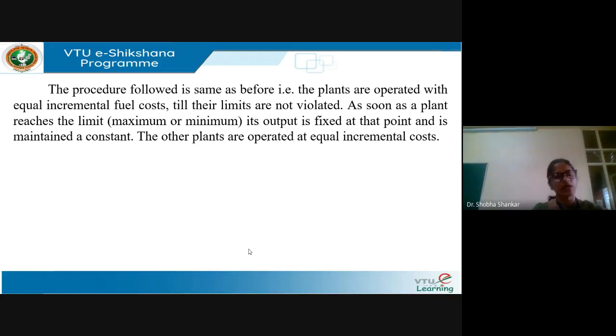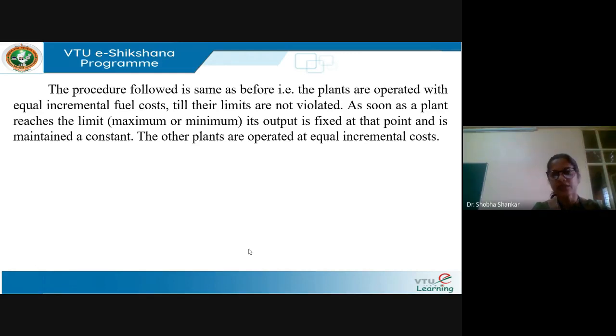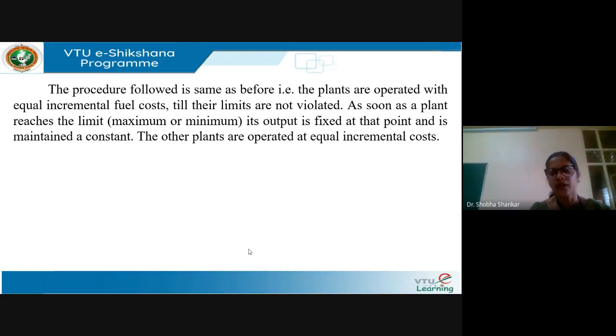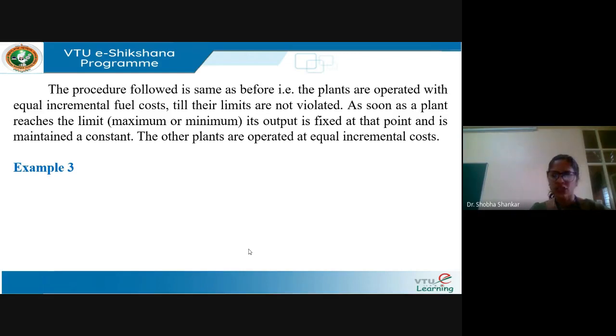Let us assume that in the system there are two generators, G1 and G2, which would supply the total load. Each generator has minimum and maximum operating limits. If any one of the generators exceeds either the minimum or maximum limit, the power output of that plant is fixed at that limit value and maintained constant. We then ensure fuel cost is minimized by operating the other plant at minimum cost. We will take up one problem to understand this concept better.